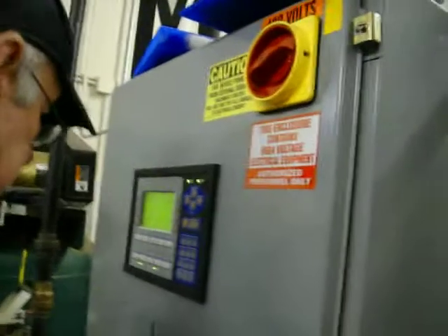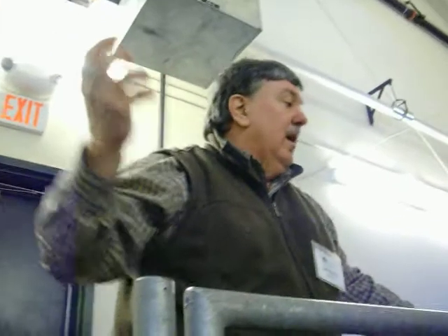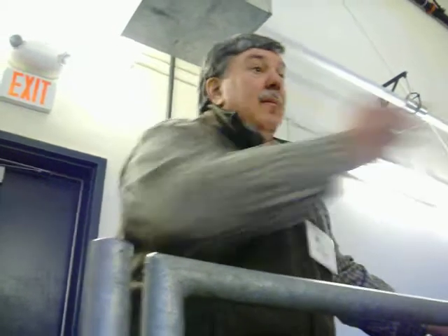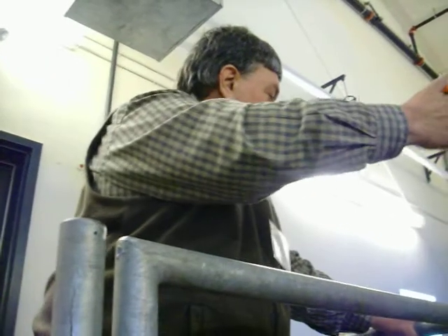The computer for the boiler looks at return water temperature. You send the water out at 185 — a little more than you would normally with a regular boiler plant — and the computer looks at the temperature coming back to see how much heat has been extracted, and adjusts the flame and the amount of fuel being sent into it.